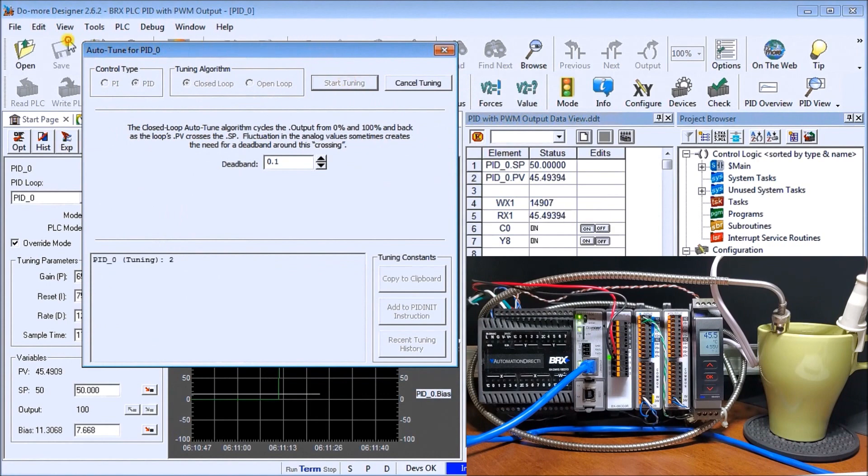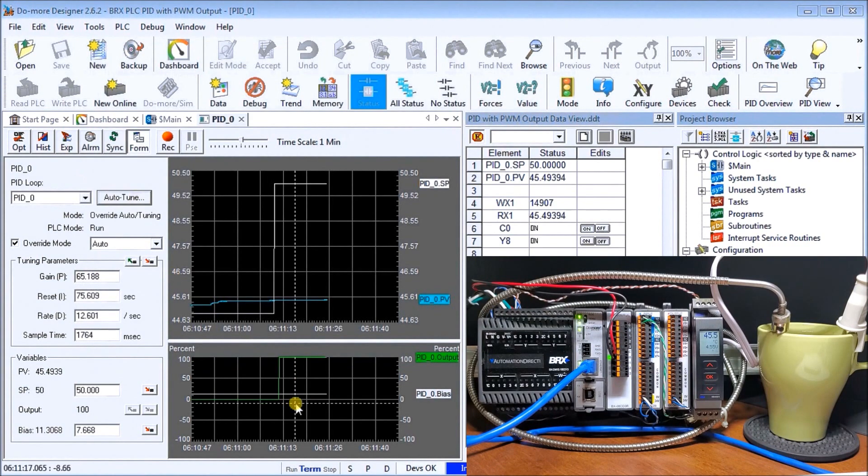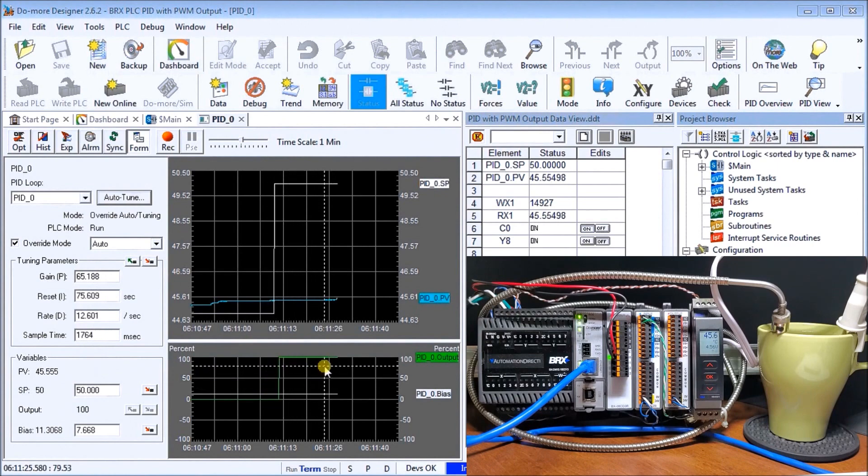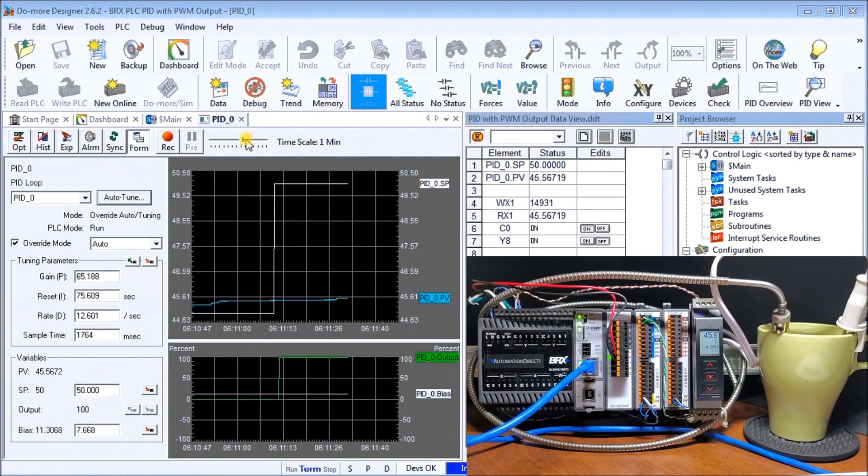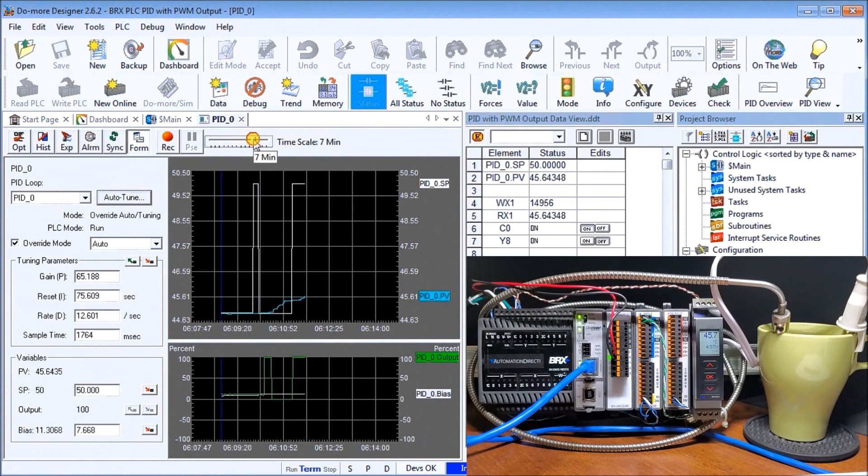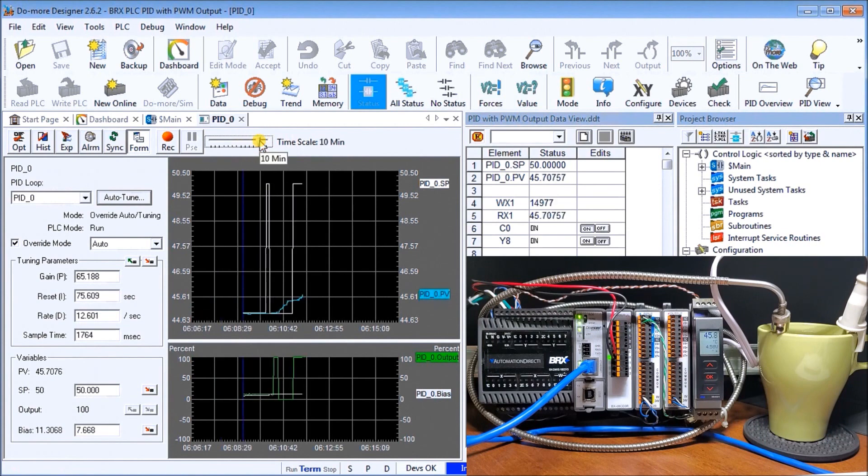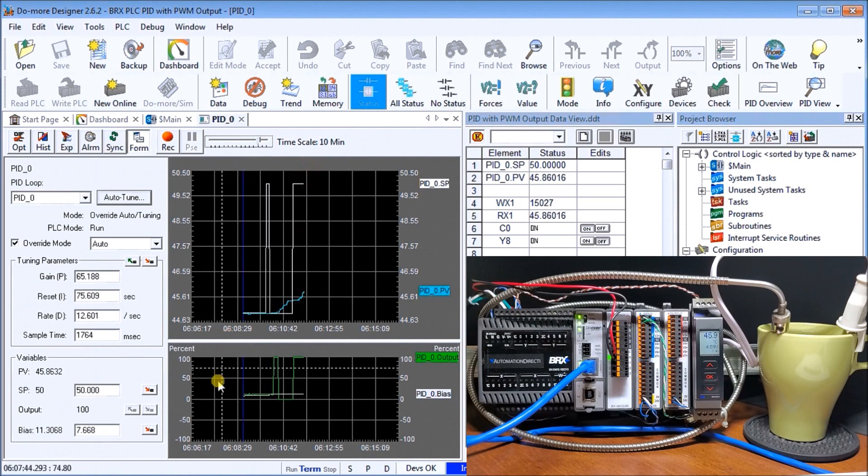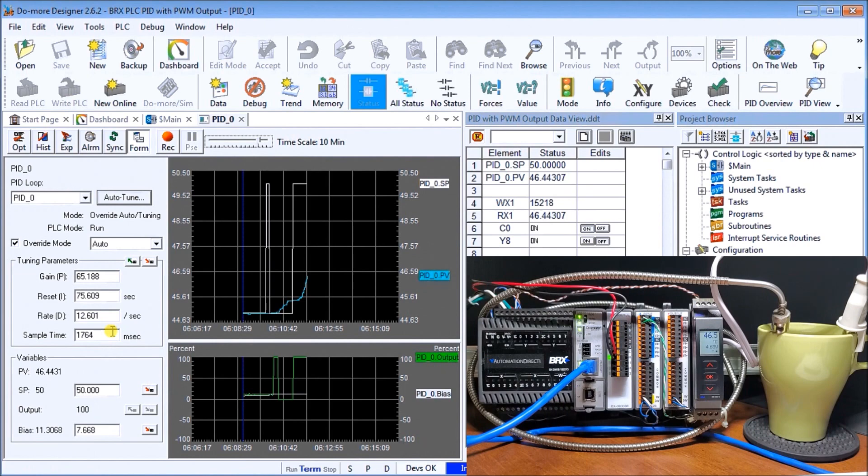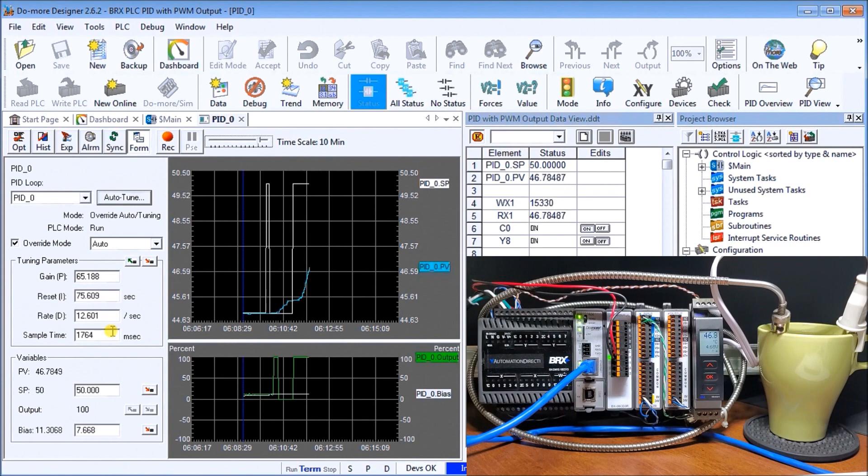Our output is on and we're starting to ramp up. Let's change our scale value to 10 so we'll see that coming up to our 50. What we want to see is it'll overshoot it, come back down below it, and then up again. Two cycles through above and below that set point and then our PID parameters will be tuned in.